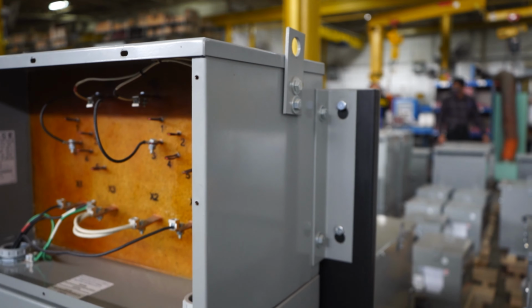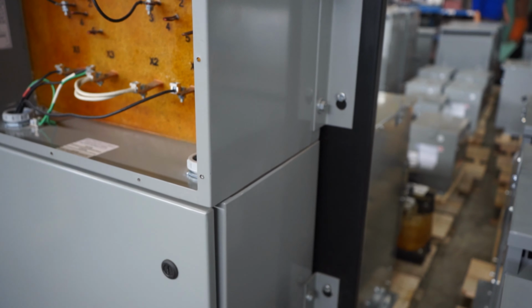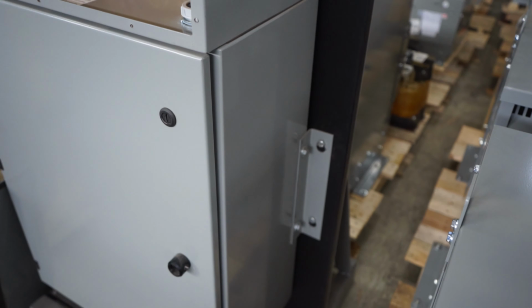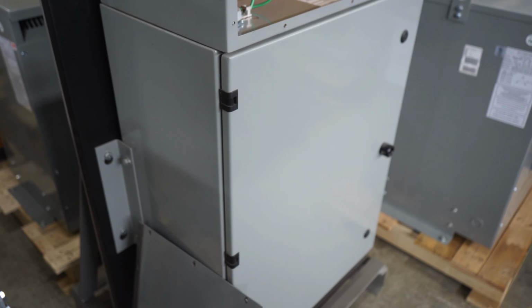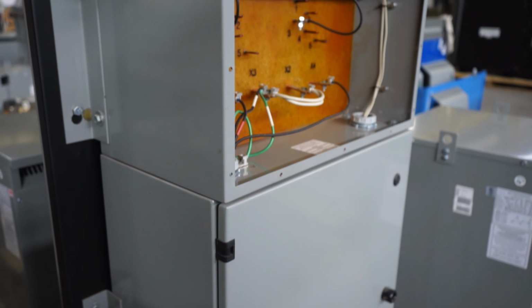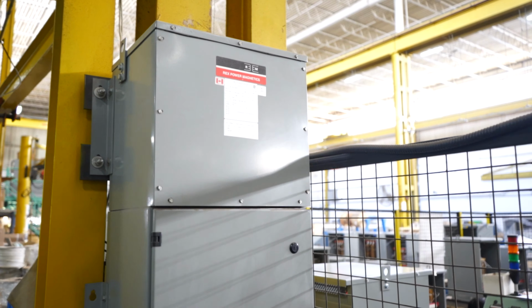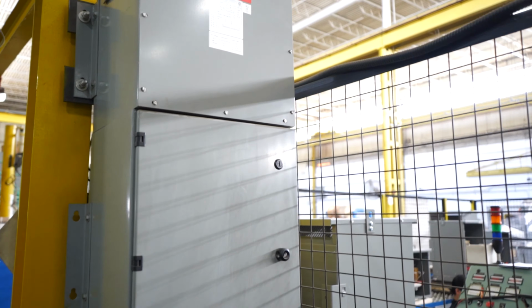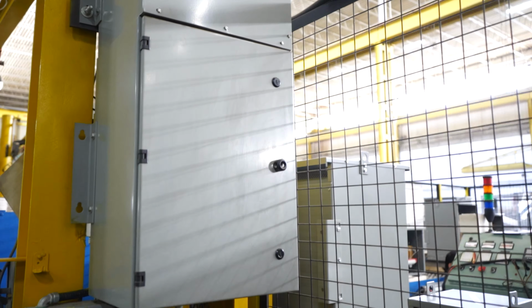Mini power centers are ideal for both temporary power installations as well as permanent installations where space is limited. In addition to saving footprint and space, installation time in the field is also reduced. Electricians only need to install a single piece of equipment, and from there, they can immediately move on to wiring.